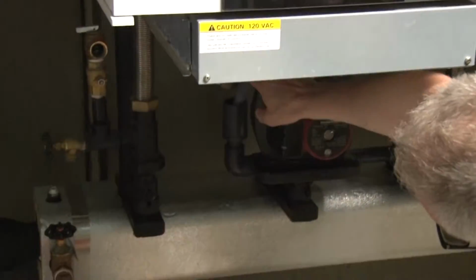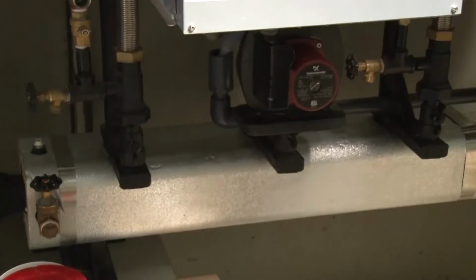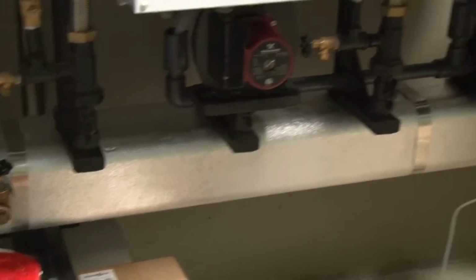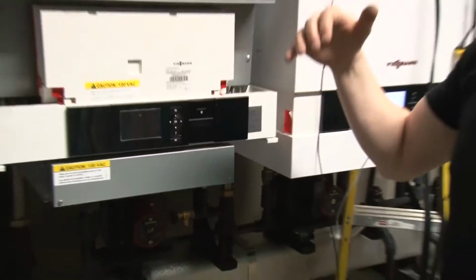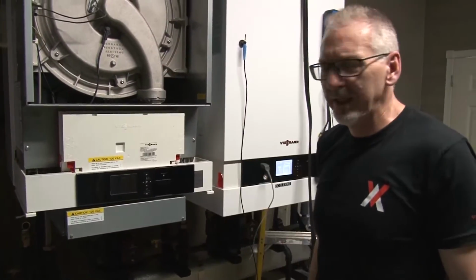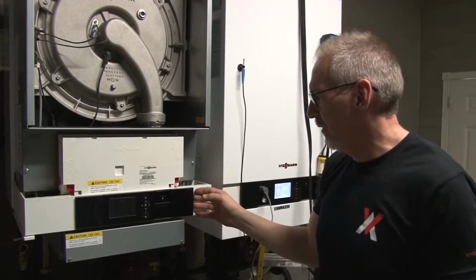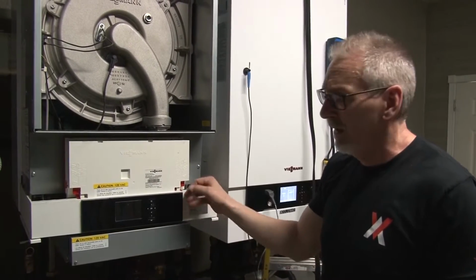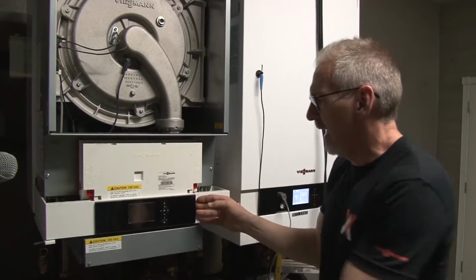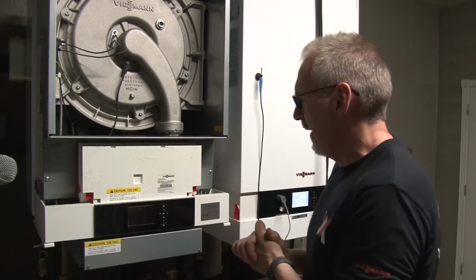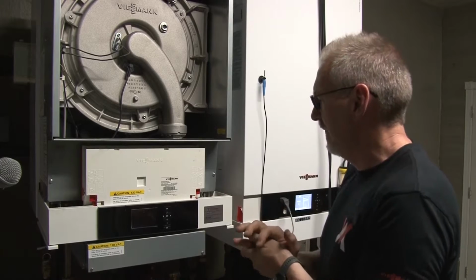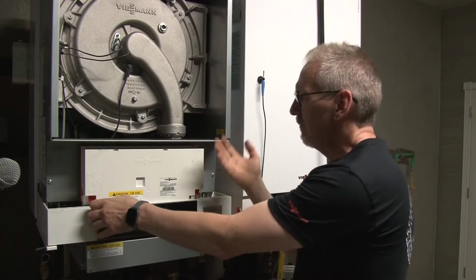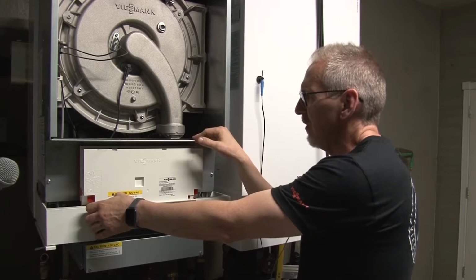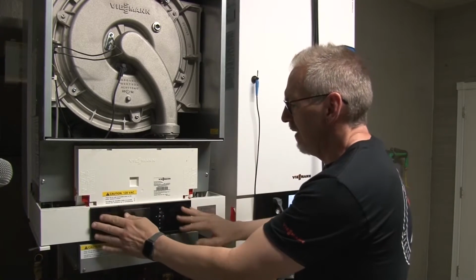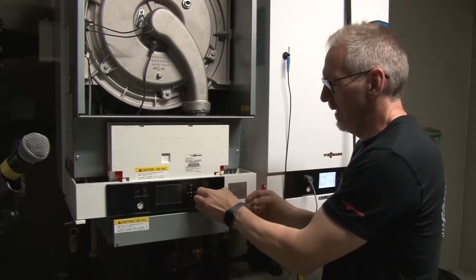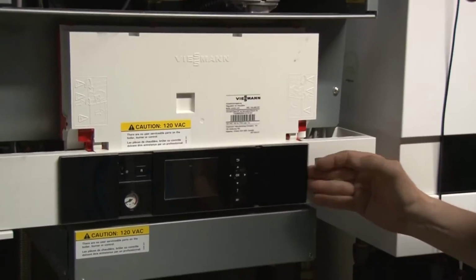And we're going to shut the gas off. In the very back here, there's a gas isolation valve. We've shut that off already. So if we pull this burner out, we don't have to worry about gas escaping out of the boiler enclosure at all. Safety first is something that we always keep in mind, so just make sure that we don't have any of those things in an unsafe condition. Once we get to pulling the burner out, that's the first step in your service. These little barn doors on the control here, where your power button is, we want to close that.